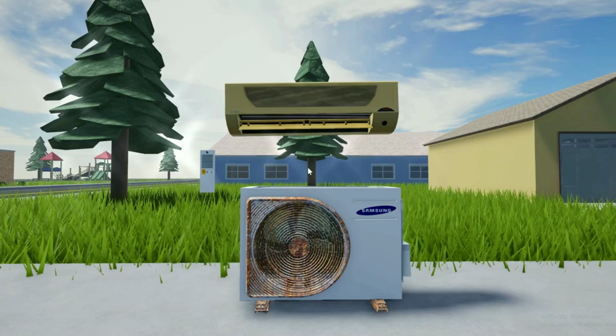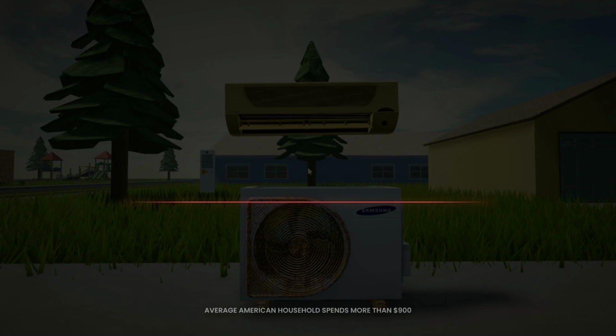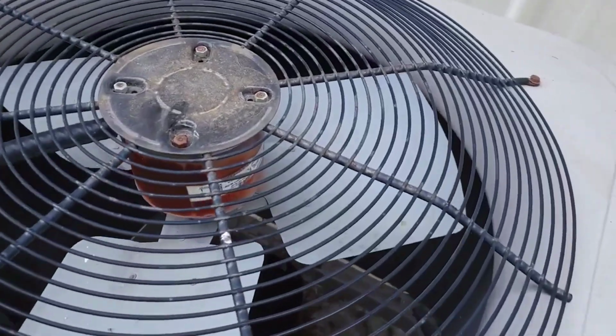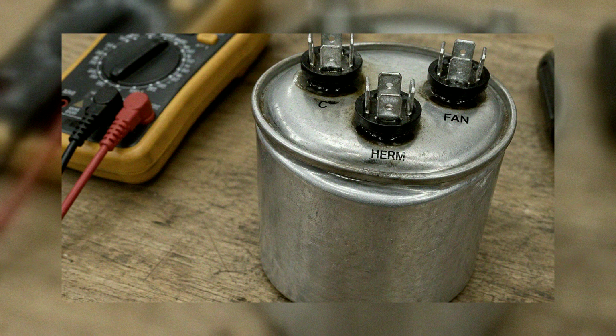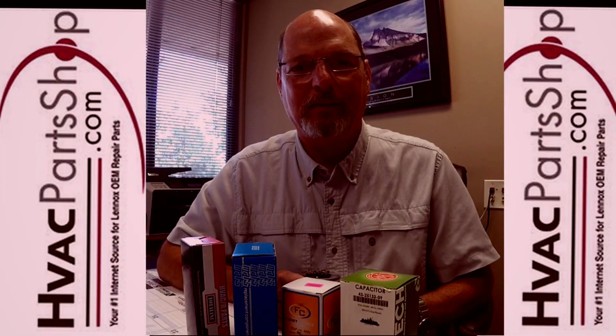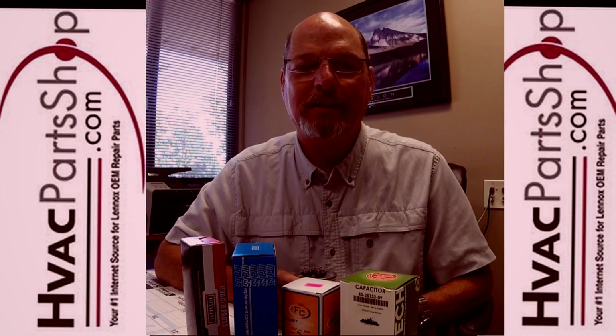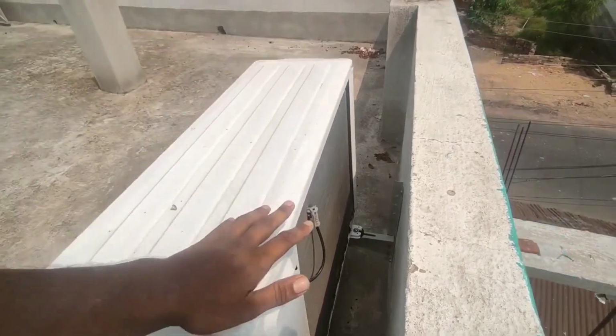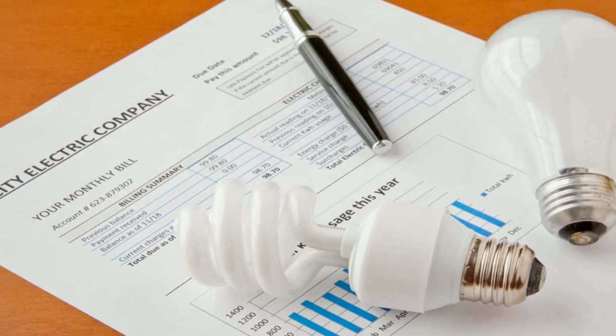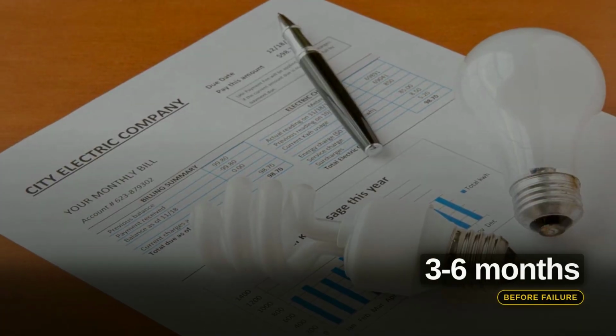The average American household spends more than $900 every year on heating and cooling. That number is not static. It moves with your system's health, and a failing capacitor moves it in the wrong direction before it ever triggers a full breakdown. A capacitor that is degraded but not yet dead forces your compressor and fan motors to work harder on every cycle. Those motors draw excess current as they strain to compensate. That inefficiency does not show up as a repair call. It shows up as a slightly higher electric bill every month for the 3 to 6 months before the unit finally quits. By the time you call the tech, you have already paid a hidden tax on the failure.